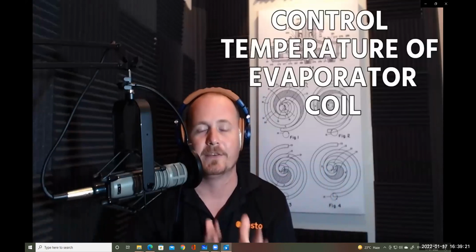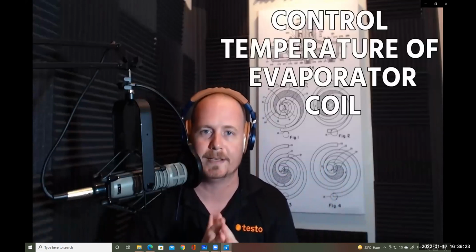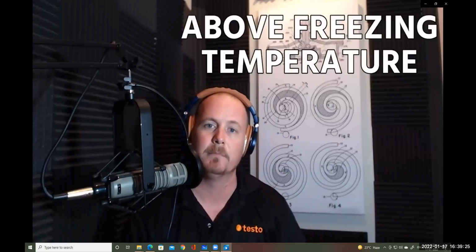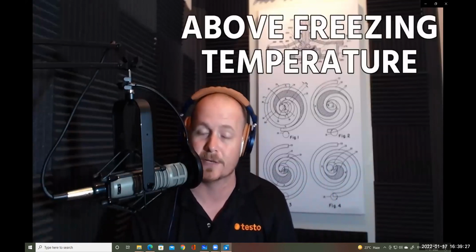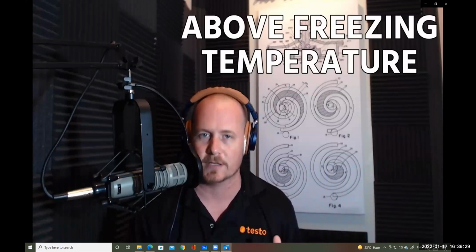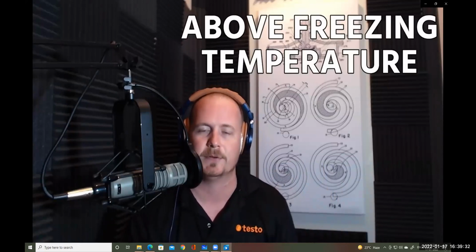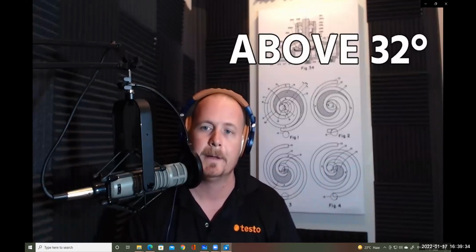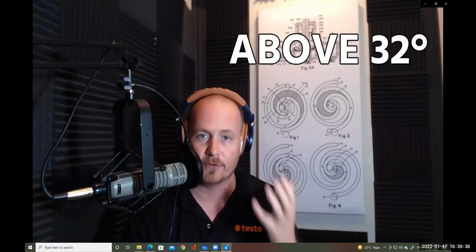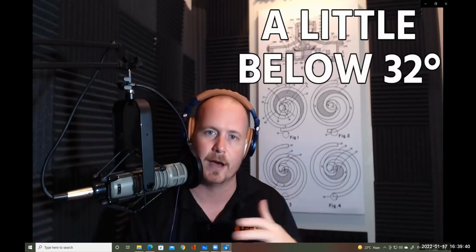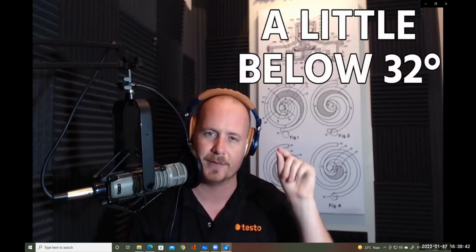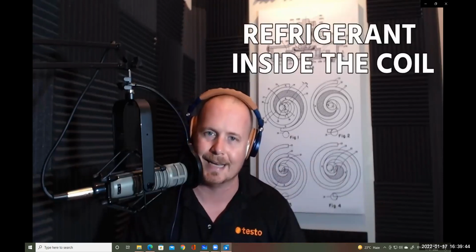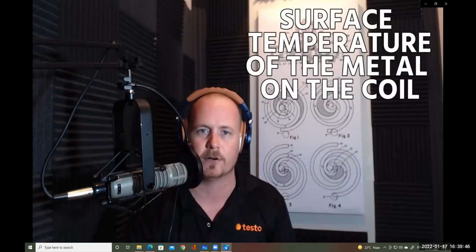It's very important in air conditioning that we control the temperature of the evaporator coil and keep it above the freezing temperature, because most air conditioners don't have any way of defrosting. So we've got to keep that coil surface temperature above 32 degrees to ensure that we don't start to build up frost and ice. Now, in practicality, you can actually get it a little below 32 and not have frost, because there's a slight difference between the temperature of the refrigerant inside the coil and the actual surface temperature of the metal on the coil. There's a slight variance there.